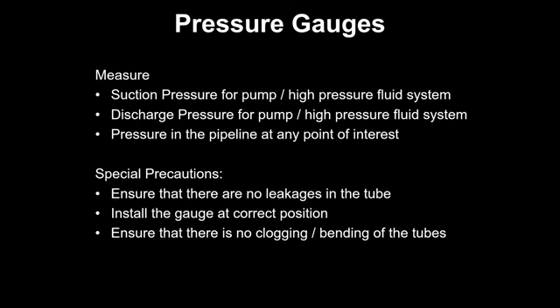Pressure gauges and manometers are all the same family. Pressure gauges are for higher values, manometers are for lower values. All we use is digital, and I think most of the auditors have digital instruments only now. It is basically for pump performance, sometimes compressor performance, and pressure drop in the pipeline. This is because the distribution system also becomes very critical, especially when you have a long piping length or multiple AHUs. Like pharma industries, where they have 100, 200 AHUs, the distribution line can be very challenging. They may not get water flow at certain points, at the extreme ends.